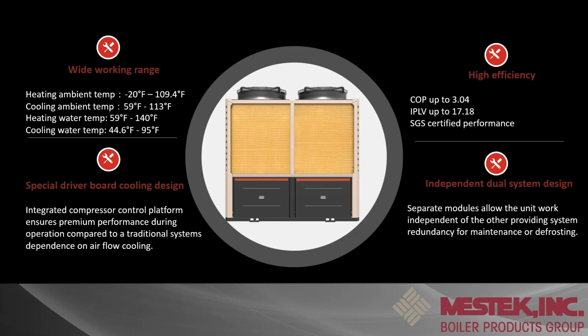Here, just to give you an idea of the working range, and again, I'll show you some charts as we get through this, the heating ambient temperature is minus 20 to basically 110 degrees Fahrenheit. Your cooling ambient out of the gate, minimum would be 59 degrees up to 113. On that low end of 59, let's say you needed to do cooling all year round, you would contact us, and there is some parameter change, and we can get down to 5 degrees. So if you had to do cooling down to 5 degrees, we can adapt to that.